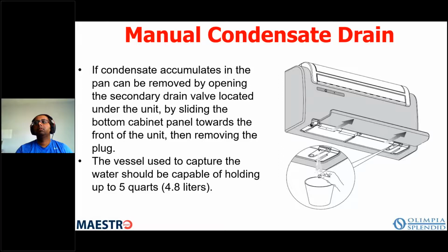And then if enough condensate builds to a level that is, say, close to spilling over, the unit shuts off. There's a secondary float that turns the unit off so it doesn't allow any water to drip out of the unit. So when that happens, it gives you a code. Then you just open up the flap like you see there on the bottom and you pull the plug out and you drain the condensate out, put the plug back in, close the flap, you're back in business, okay?